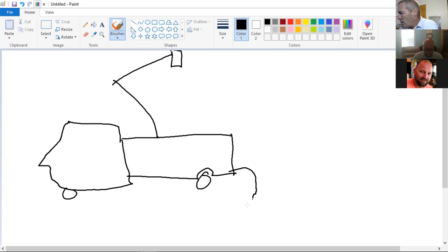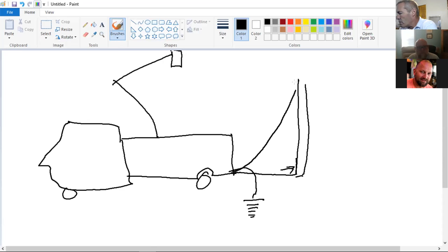Some companies make you go to a screw down rod, which you put in the ground. Or some companies go to the coil ground, where there's actually a ground going down the pole attached to that. Some companies carry it all the way up to the neutral. Our practice was to use a screw down ground, manually, like a T-bar with a corkscrew at the end. You screw it down into the earth and attach your ground to it right there.